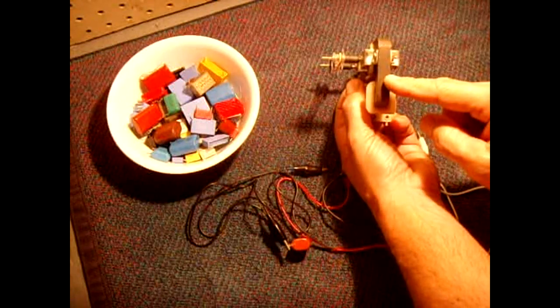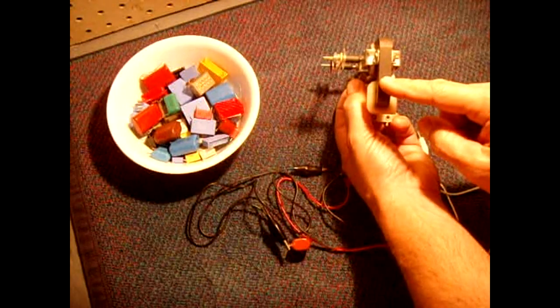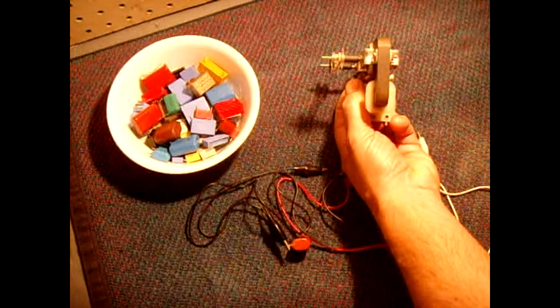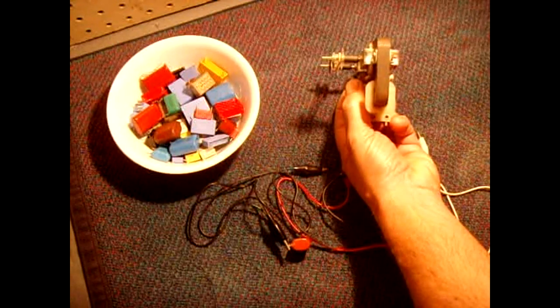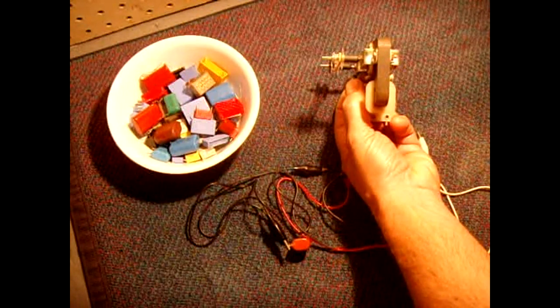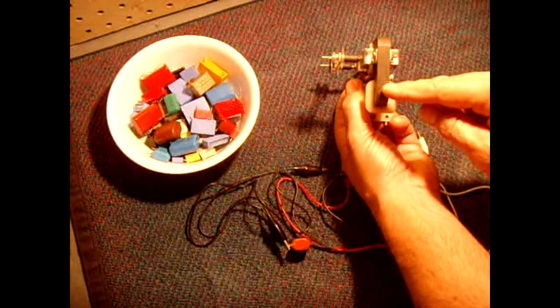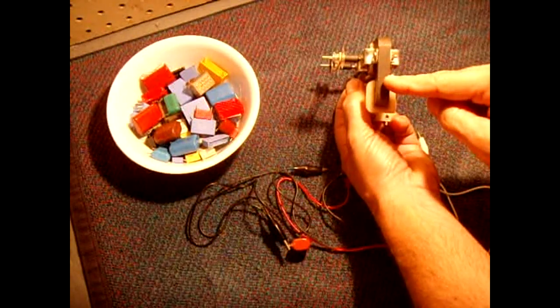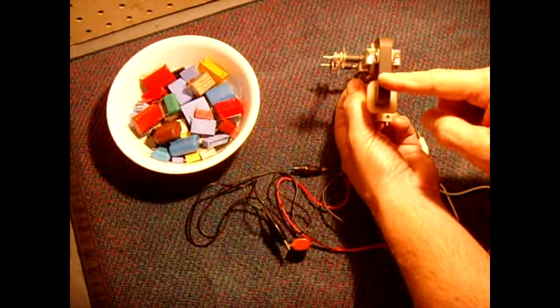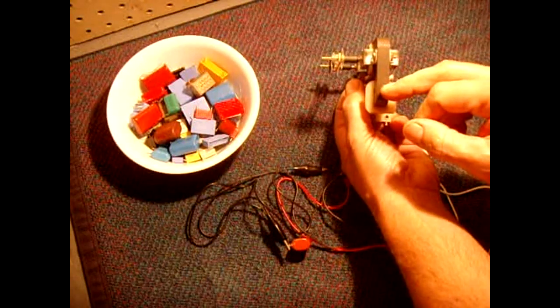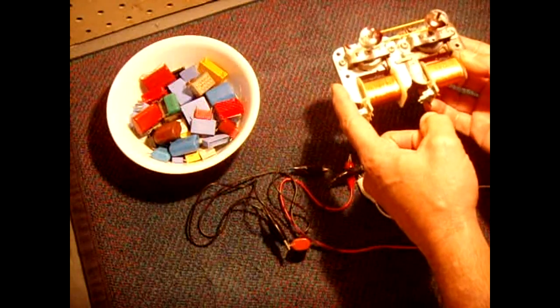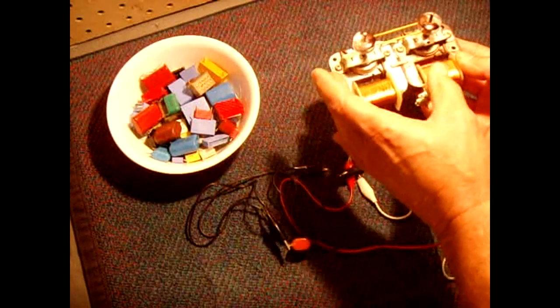I looked up the part number. You can see part of it was exposed. It said 6309-230. When I looked it up, I came across a SP6309-230 shaded pole motor made by Johnson Electric. And the rating of that motor is, as shown on the label, 220 volts forward slash 240 volts, 50 Hertz. Now you know why the label was cut before the 2 and 240, because he didn't want you to see that it's actually a 220-240 volt motor, just like the other one was in his video. So for all practical purposes, both motors are the same.